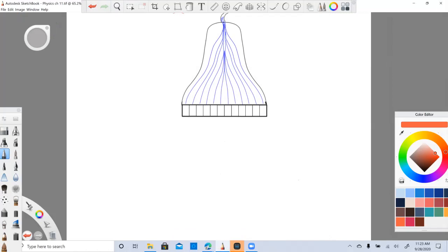So I'm just reading here, page 168, single element transducers. Mechanical probes are technically simple, have been replaced by more sophisticated designs. Generally, modern transducers called arrays contain multiple active elements. What you start with is a single slab of piezoelectric material, lead zirconate titanate, cut into a collection of separate pieces called elements. Each active element is connected by a wire to its own electric circuitry in this ultrasound system. Each element is acoustically isolated from its neighboring crystals.